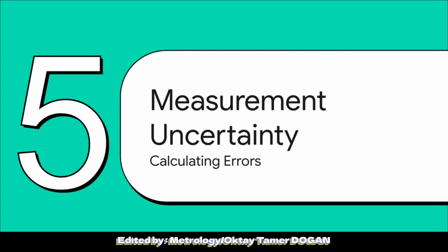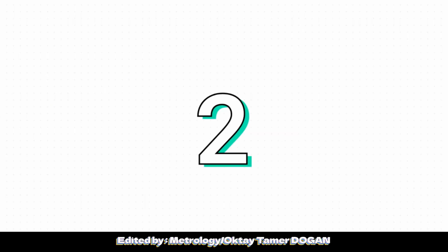All right, Section 5. Measurement uncertainty and calculating errors. We've set the stage, we've controlled the environment, we've run the test. Now we arrive at the most complex but absolutely vital part of this explainer, the rigorous math required to actually prove a device's accuracy. Before you even touch the calculator, Euramet CG17 dictates a really crucial rule of thumb. The measurement uncertainty of your laboratory reference device must be at least 2 times better than the uncertainty you are trying to assign to the device you're testing.